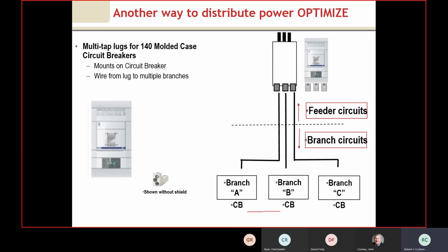Where the optimization might come in is using a multi-tap lug, shown at the bottom, connected directly to the circuit breaker we're using. This minimizes the need for a power distribution block, cutting down the space factor as well as the additional cost. So this is an idea for optimizing the panel.